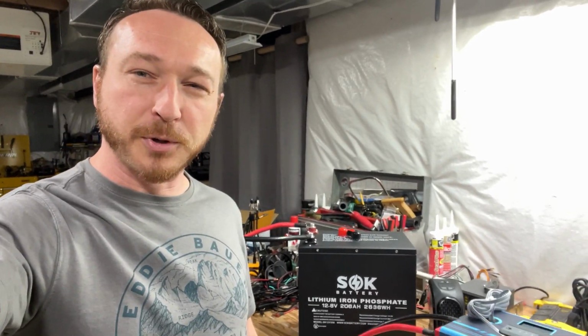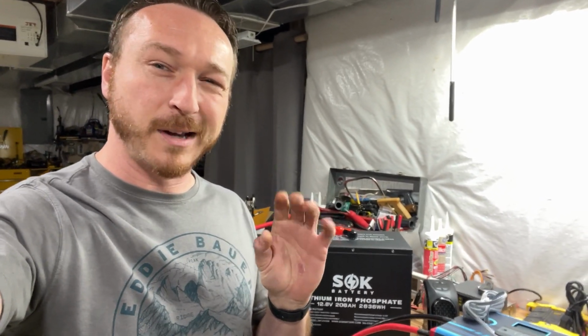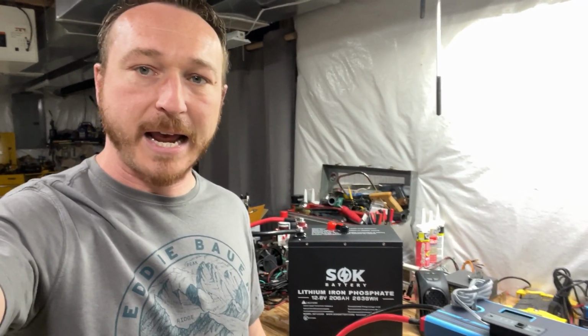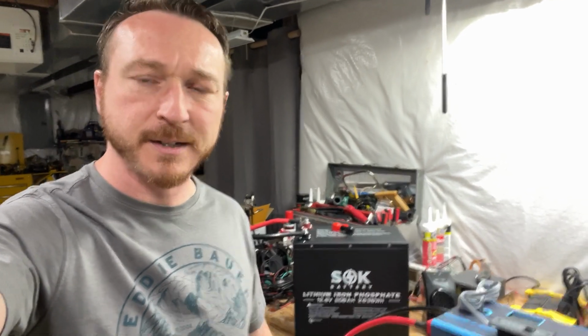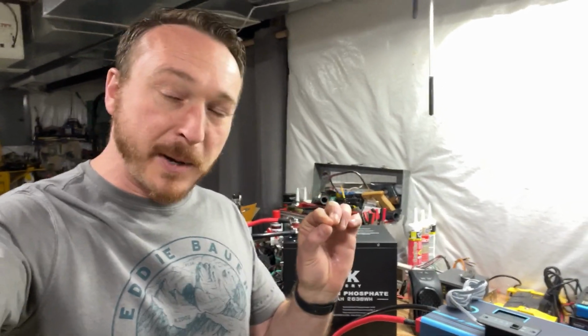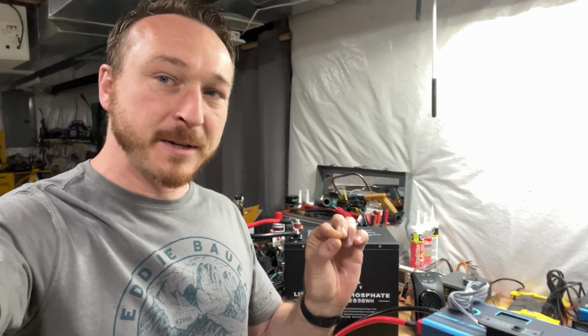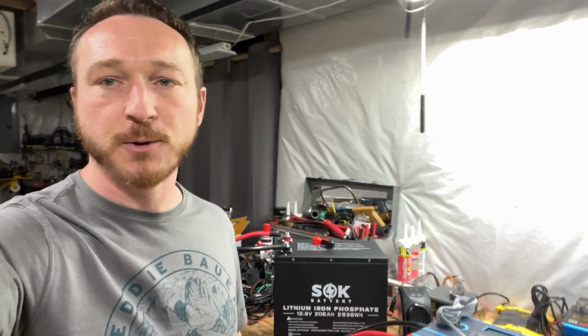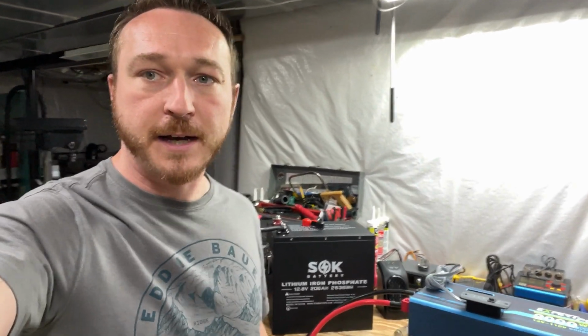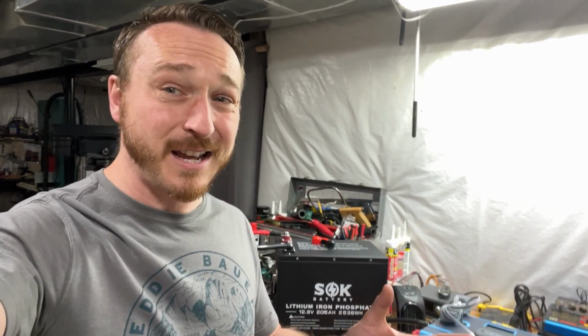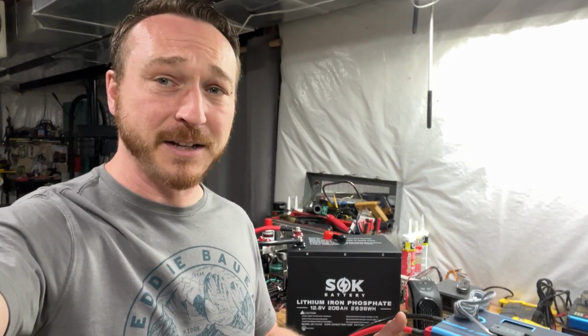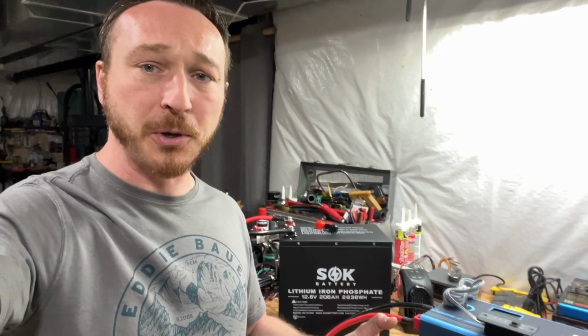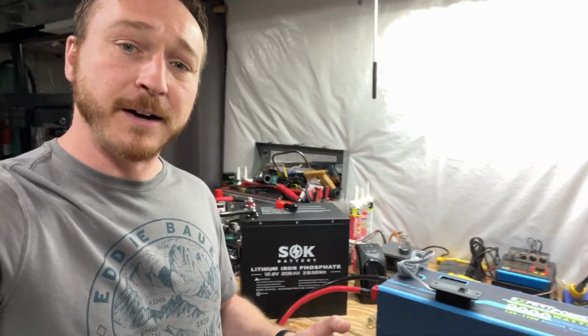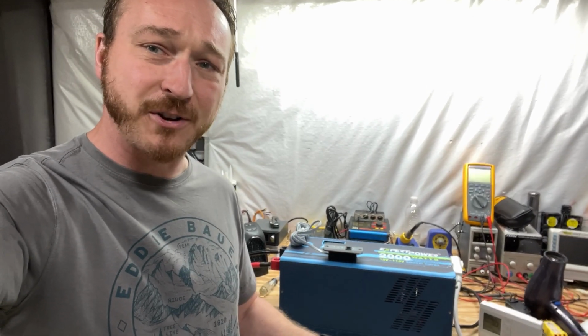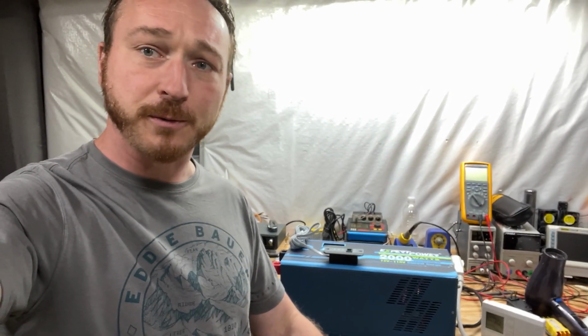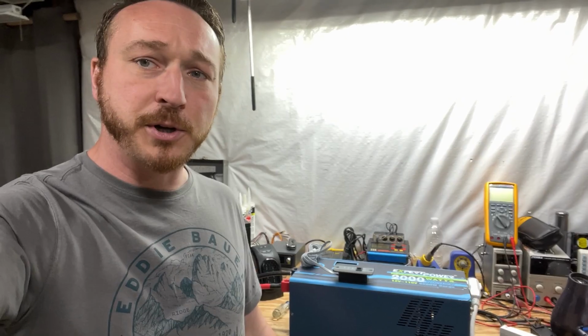I did see a brief spike on the BMS output amperage reading - there's an app that hooks up to this thing, because it's Bluetooth, of course it is - and it showed a brief spike to somewhere close to 180 amps, but it was just instantaneous. As soon as the compressor gets turned over, it drops back down to just like 60 amps, which is still crazy, still a lot of power, but it's running through the Expertpower at about 700 watts at full speed. So I think we've got a real working system here.